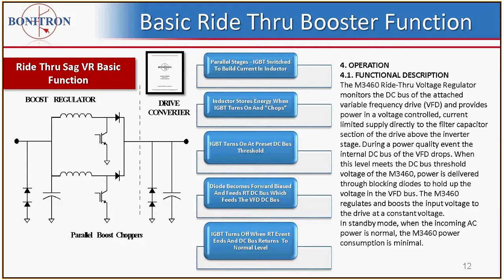During a power quality event, the internal DC bus of the VFD is going to drop. When this level meets the DC bus threshold voltage of the 3460 or M3534, functionality is basically the same for both units. Power is delivered through blocking diodes to hold up the voltage of the VFD DC bus. The 3460 regulates and boosts the input voltage of the drive at a constant voltage. In standby mode, when the incoming AC power is normal, the 3460 power consumption is minimal, as we discussed in our last presentation.